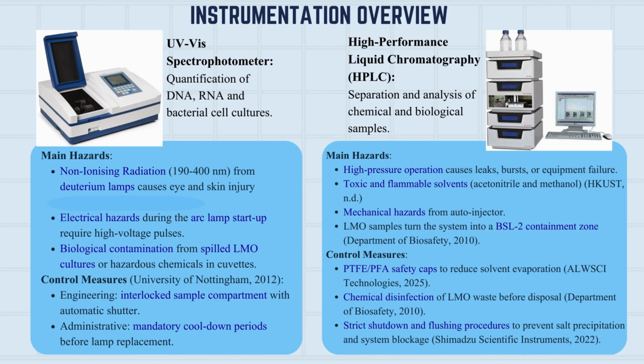The UV-Vis spectrophotometer quantifies DNA, RNA, and bacterial cultures. Its main hazards include non-ionizing UV radiation from deuterium lamps, which damages the eyes and skin, electrical hazards during high-voltage lamp startup, and biological contamination from spilled LMO samples. These risks are controlled through engineering controls such as interlocked sample compartments and administrative measures like mandatory cool-down periods before lamp replacement.